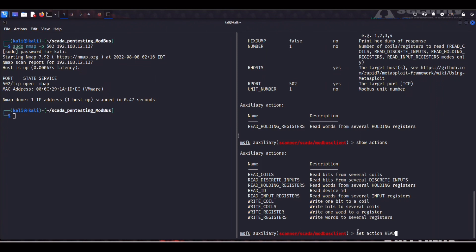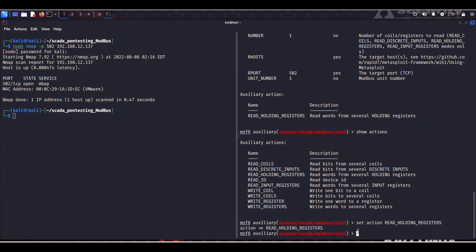So we can set the action to read holding register. Now we set the data address at five which is going to read the sixth value. Remember that arrays start at zero and not at one. So we're going to be reading the sixth value.